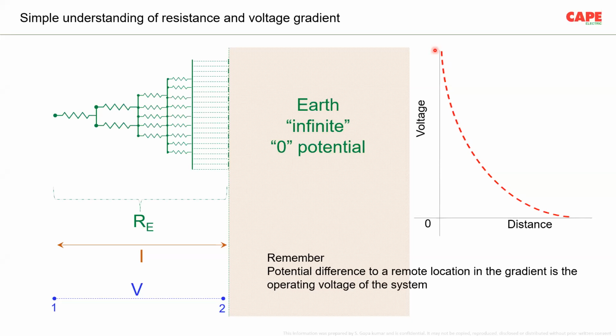I used to get calls from users. They say that we have to design an earthing system. Fault current is 50 kiloampere. Soil resistivity is 50 ohm meter. So please help us in making an earth grid or an earthing system for 50 kiloampere. Now, once I ask what is your demand, they say the touch and step potentials must be lesser than 2 kV, 1 kV, or 600 volt or some voltages.